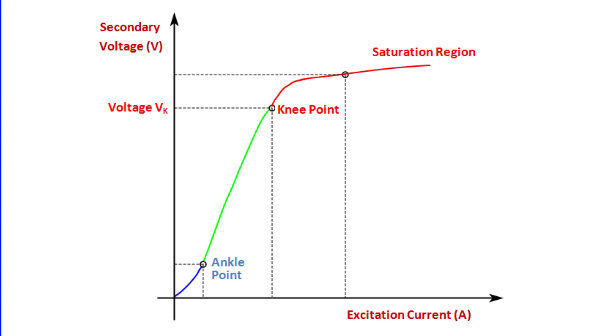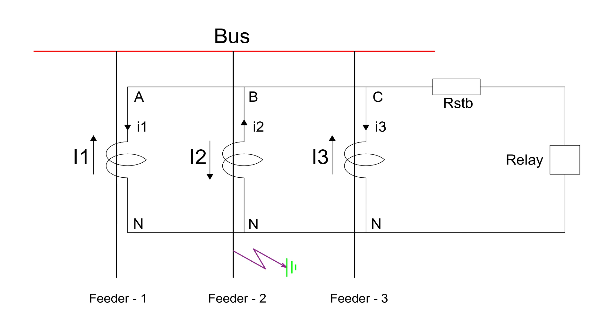The worst condition occurs when a CT gets completely saturated. Therefore, we need a way to make the relay insensitive to through faults, which is where the stabilizing resistor comes into play.